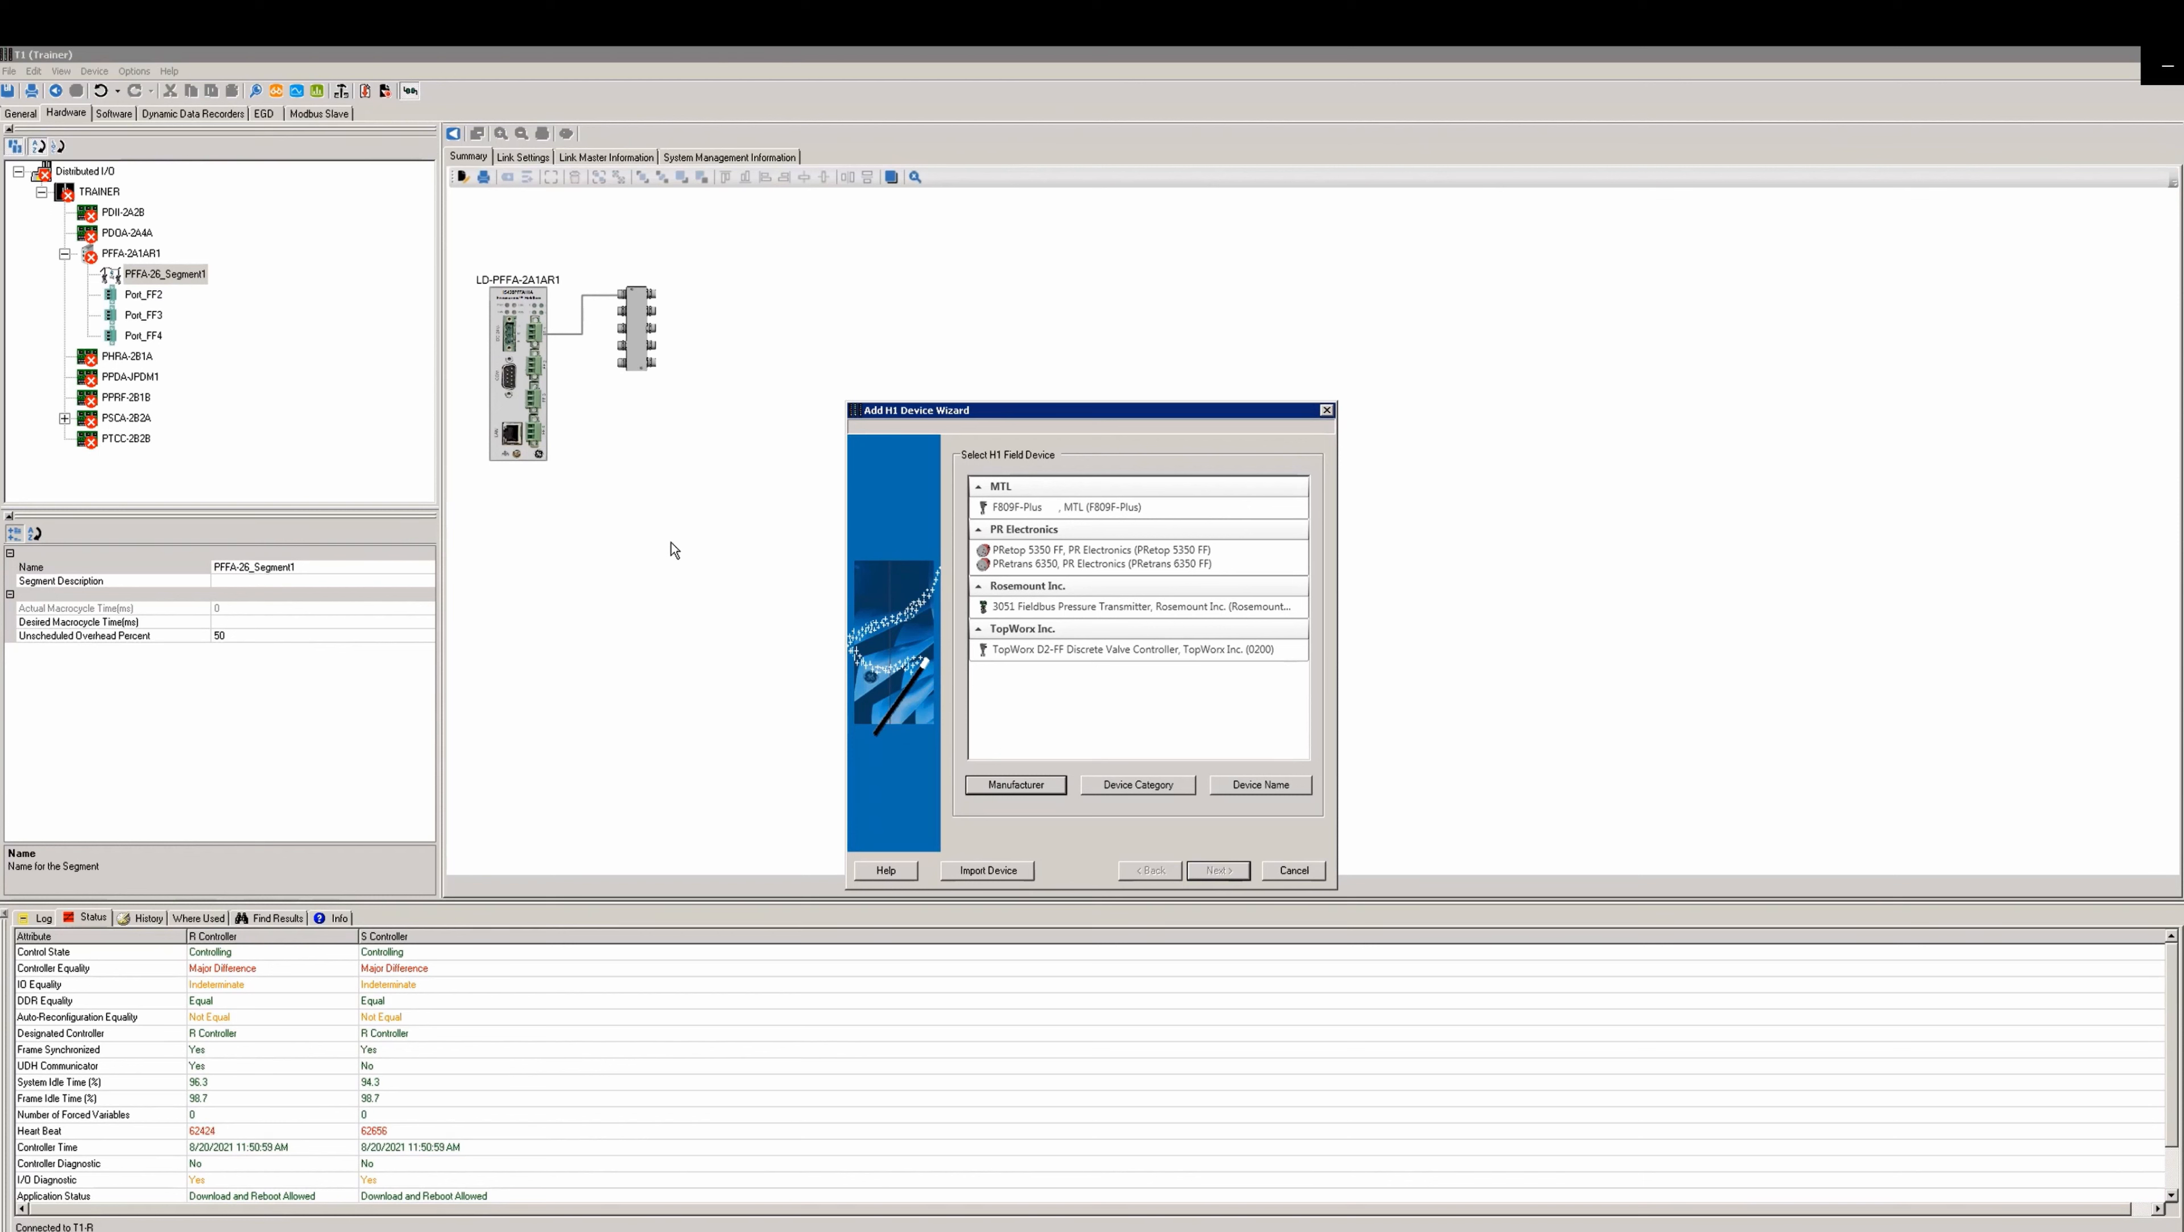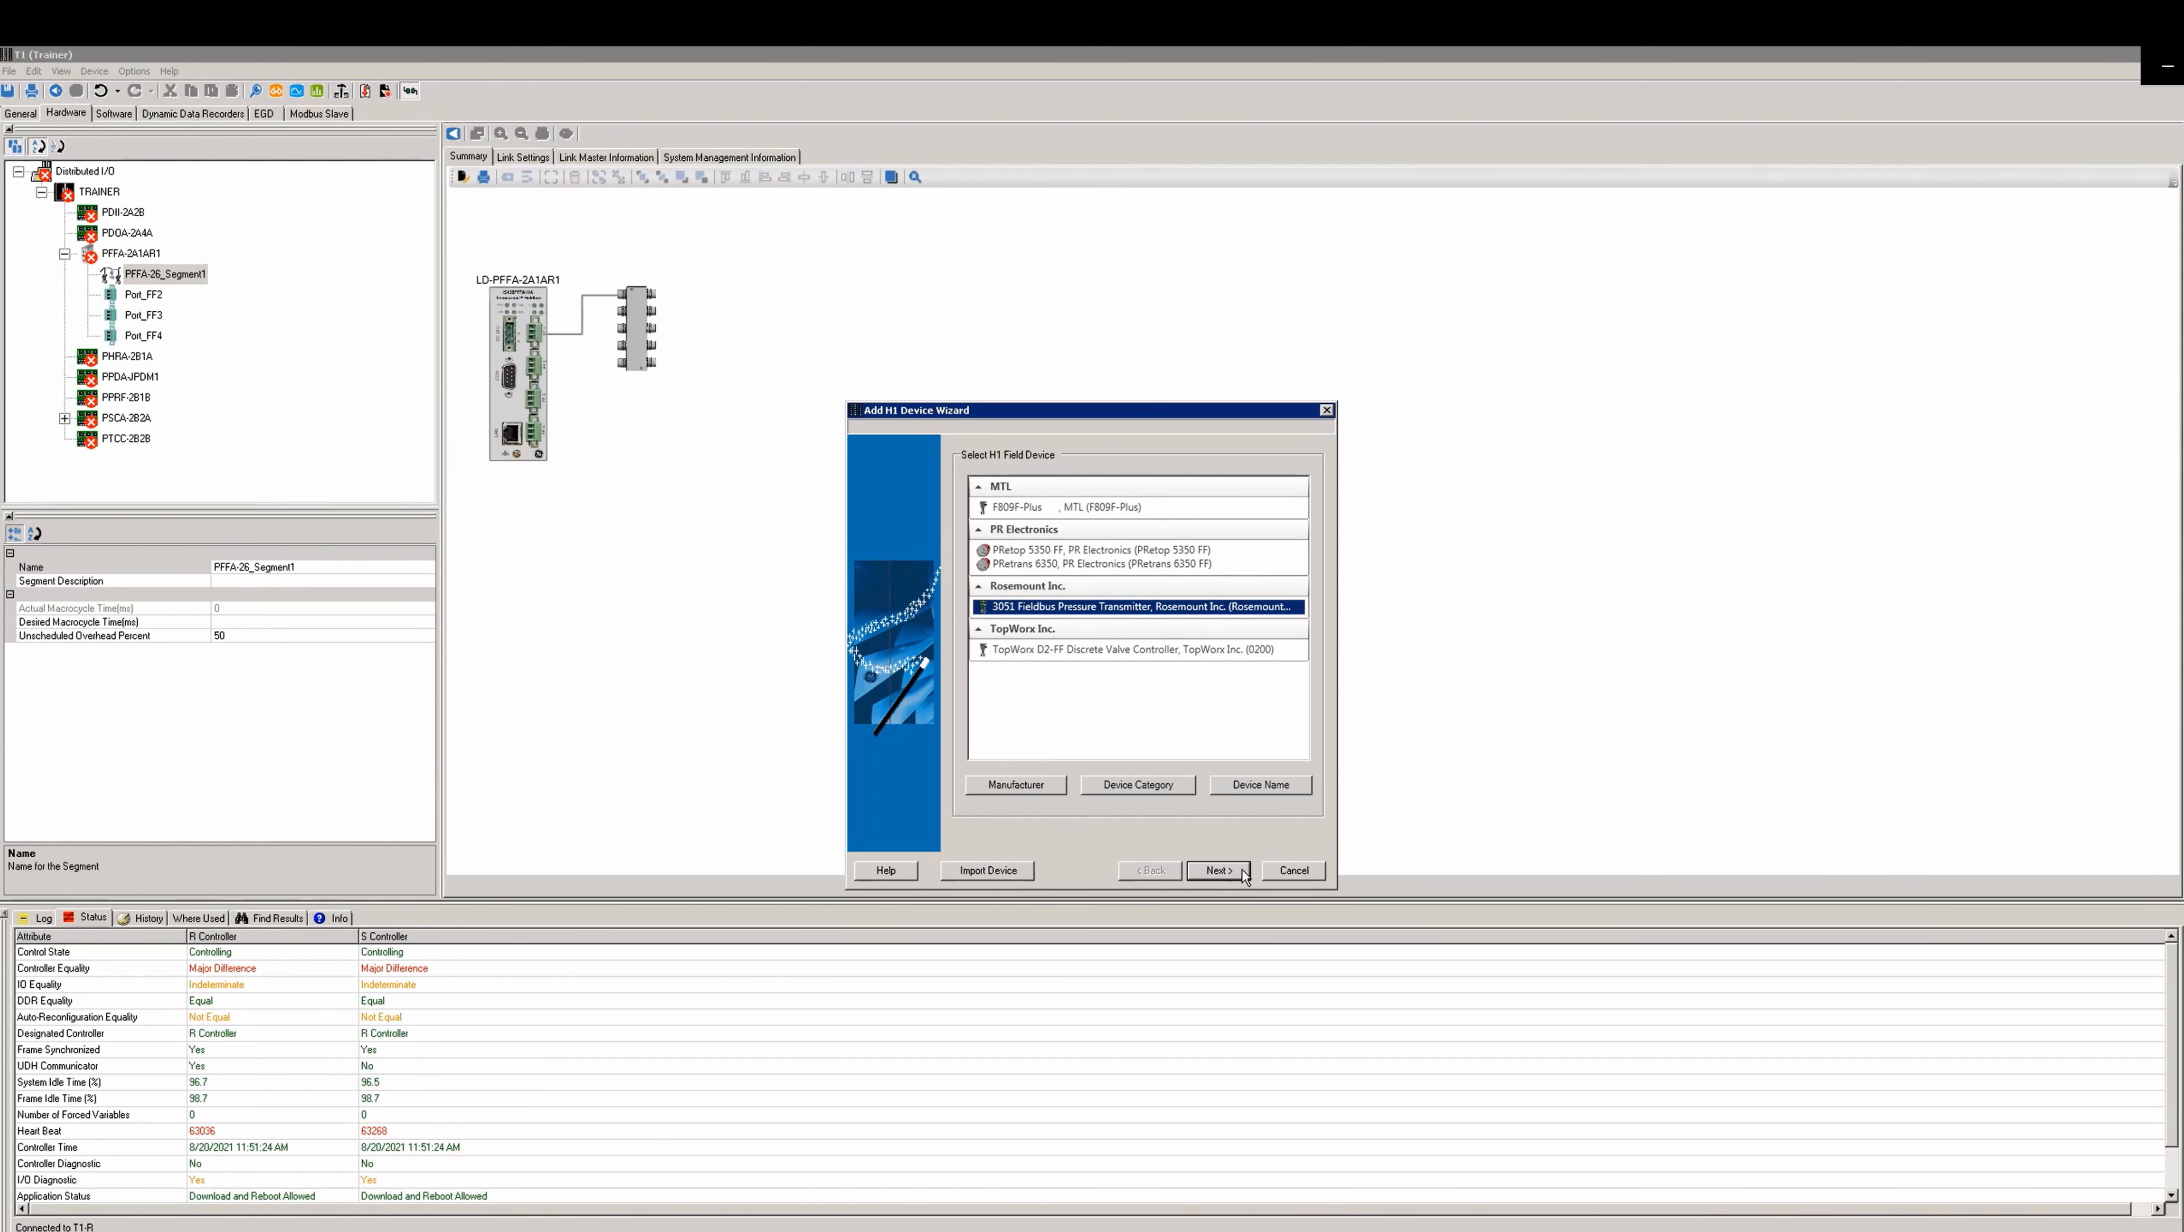When you do this, the add device wizard will pop up. Now you can select the device. In this case we're using the 3051 and we're using a revision 8. If the device you're using does not appear here, then you have to add the DD file for it through the device manager. We will cover that in a different video.